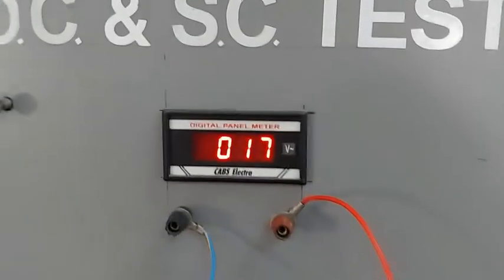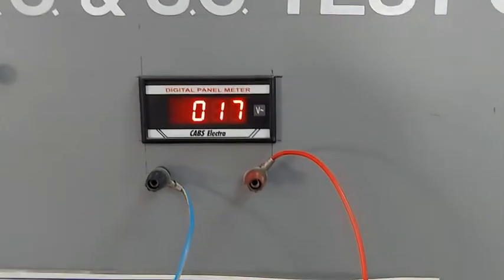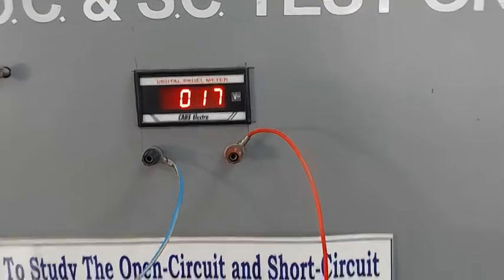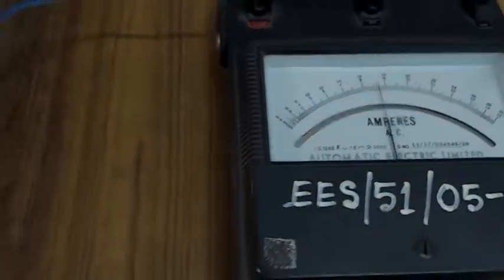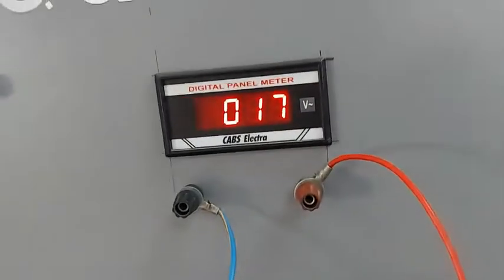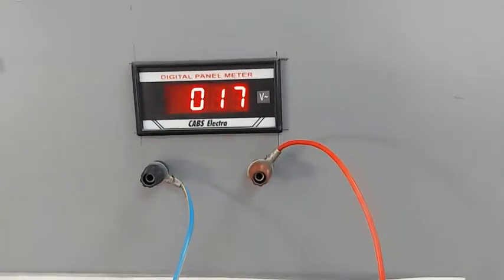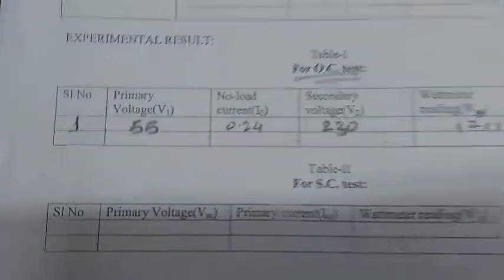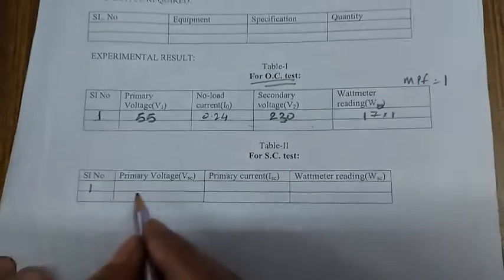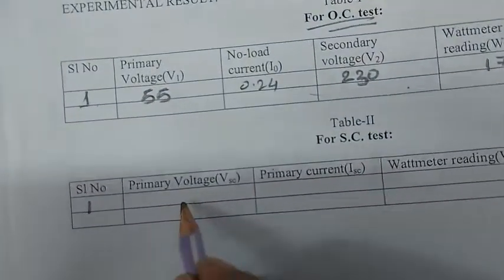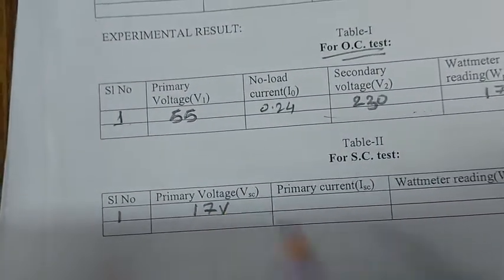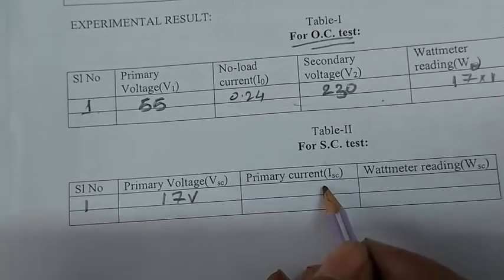So 18 is very less, 18 or 17, so it comes under the range mentioned in the manual. Now we will note down all the powers, primary and secondary ampere readings, and also the voltmeter reading of the primary winding, so that we can calculate all the circuit parameters as explained in the manual. Here we can see the primary voltage, so we will note it down as 17 volt.